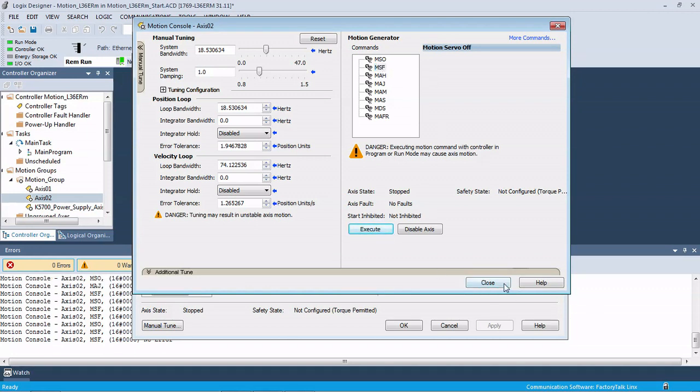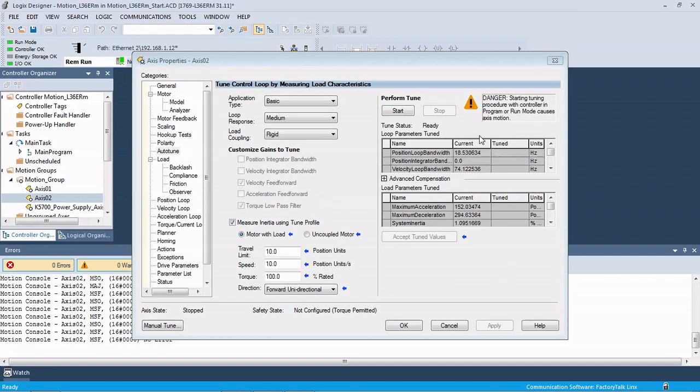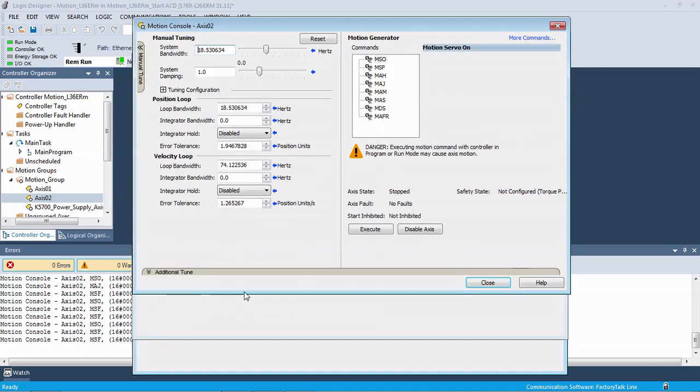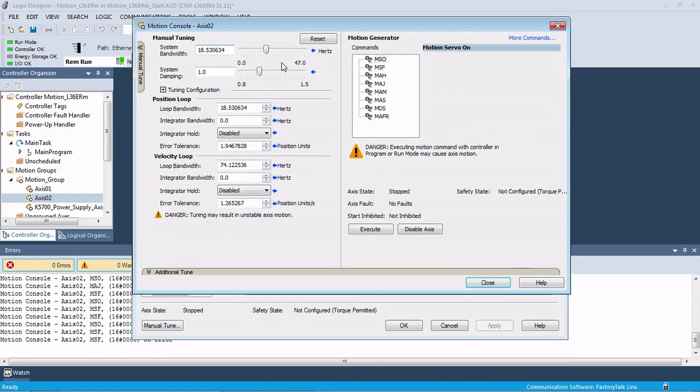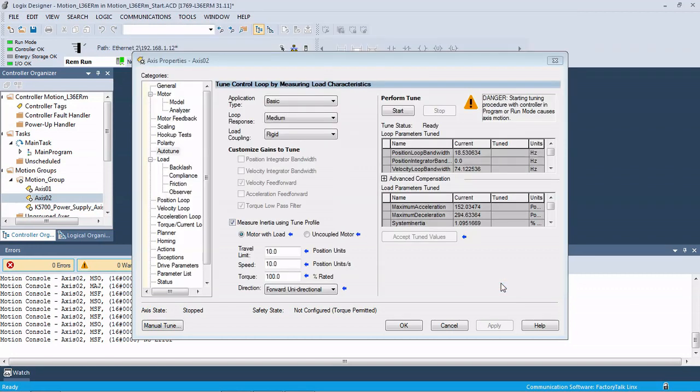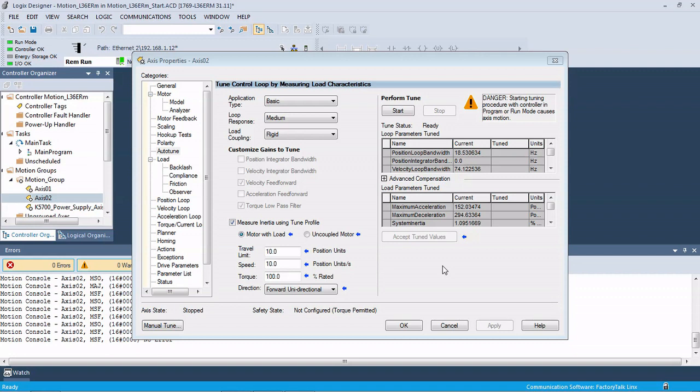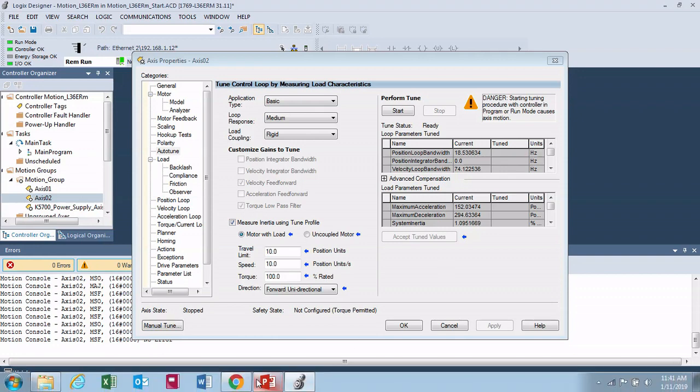Let's disable our motion servo and turn it off. From here we could run an auto-tune and then come in and mess with our loop gains and things like that to try to get this tuned the way we want it. And then any time there's a change in the mechanical side of things, as belts wear or chains wear, you're going to have to come in and retune the motor. So Rockwell has built this nice tool called Load Observer, which will track those changes and tune the motor on the fly continuously, allowing you to start up these motors without ever having to tune them.